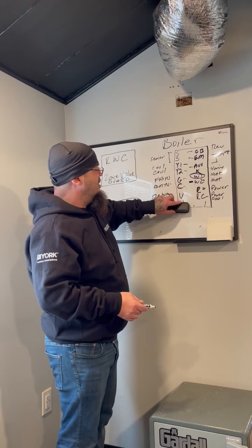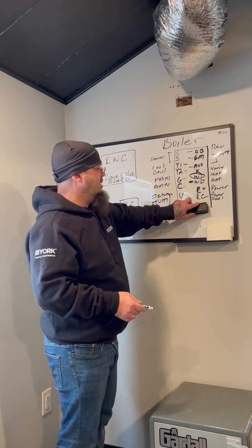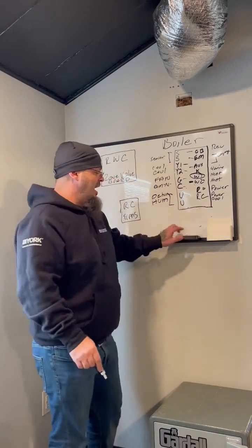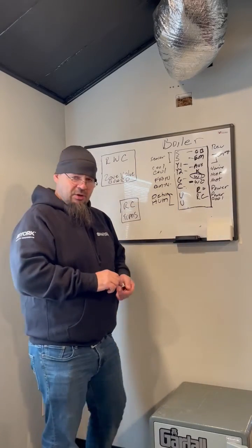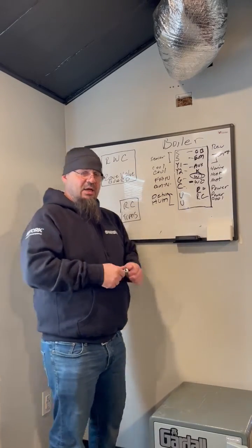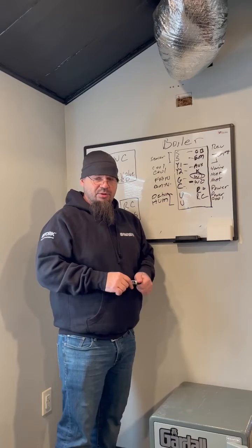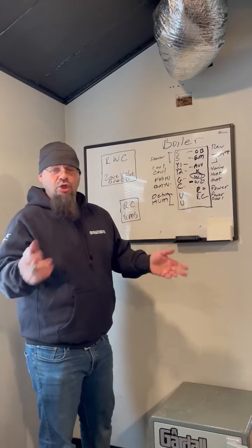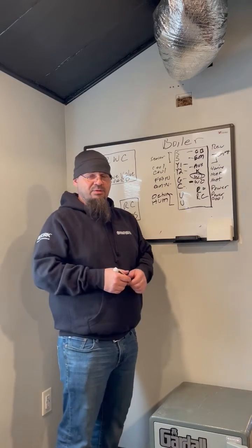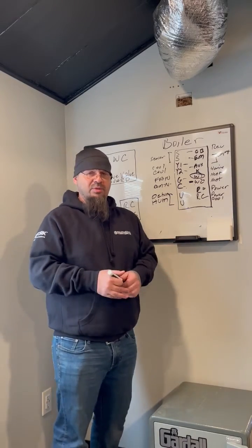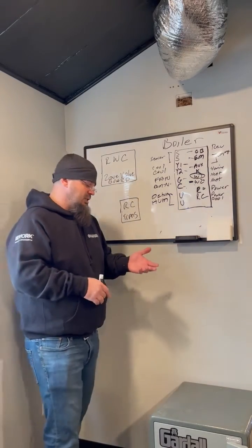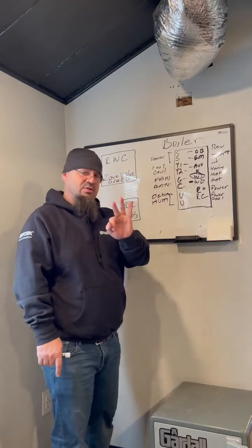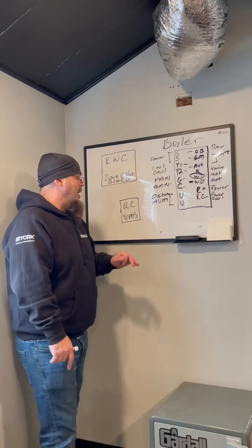So what you end up with is somebody calling me and saying, hey, I can't get this Nest to work on my boiler system. And I say to them, well, let's go downstairs and look at the control. Do you have these terminals on your boiler control? And they say, no, it just says TT. And I say, you cannot get that power stealing thermostat to work without doing some additional work. And the additional work looks like this. One, boilers usually only have 2 wires. You need at least 3 to use a power stealing thermostat.